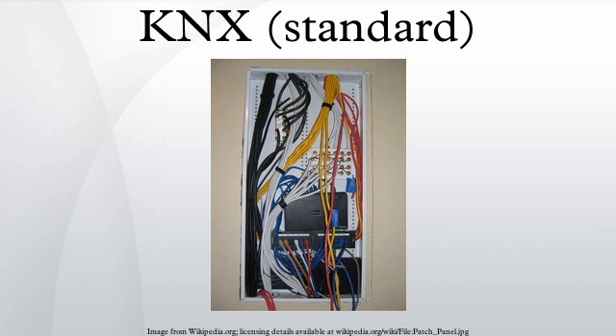Actuators receive data telegrams which are then converted into actions. This can include controlling blinds, dimming lights or controlling heating and air conditioning systems. Actuators consist of a bus coupler and an application module with a corresponding application program, which is loaded into the devices together with the project design and commissioning software via an interface connected to the PC and the bus.